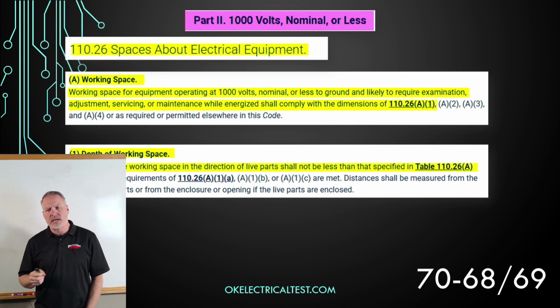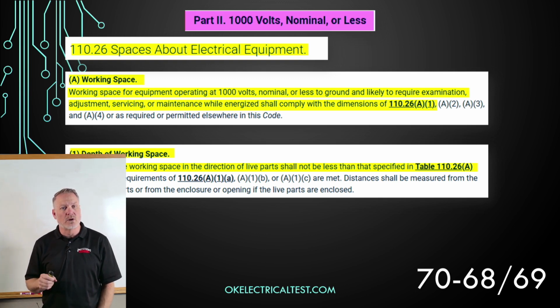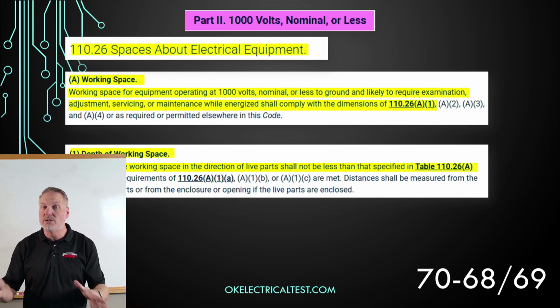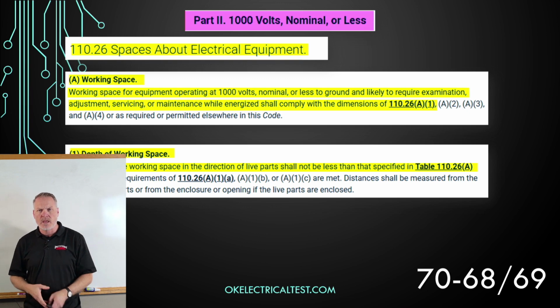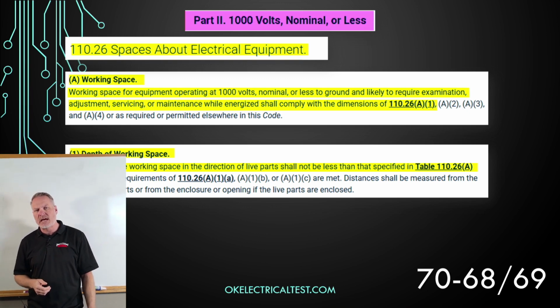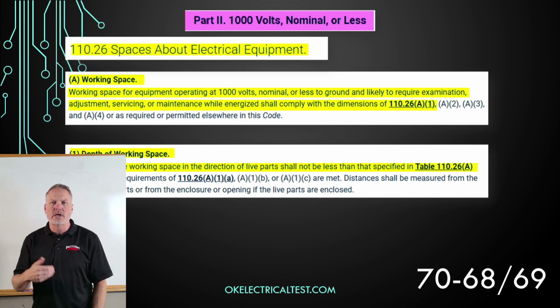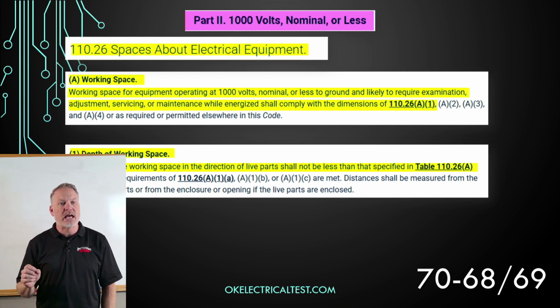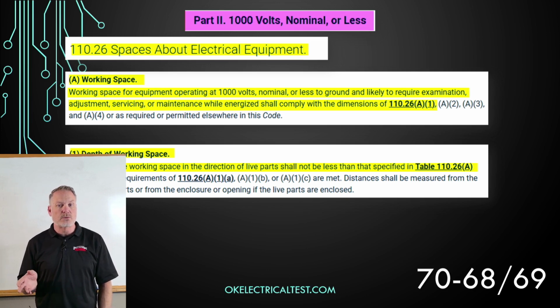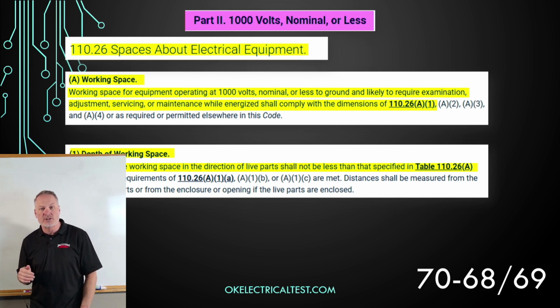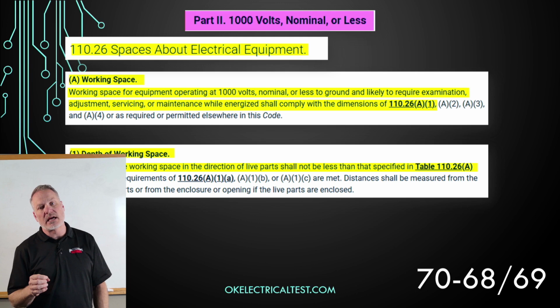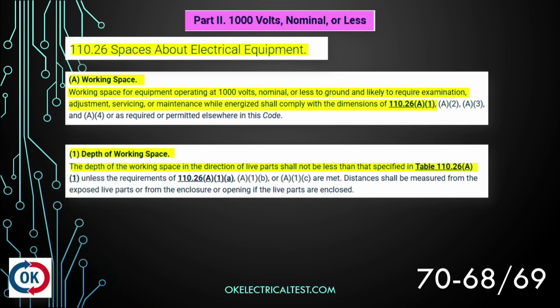Let's go down to part 2. So page 68, spilling on to 69. Part 2 is dealing with only installations that are 1,000 volts nominal or less. So remember, part 1 was general regulations. Now we're getting more specific. Hey, by the way, these regulations are only for 1,000 volts and under. And so we're going to take a look at 110.26, spaces about electrical equipment. And we're going to go to letter A, working space. Down below there, we're going to highlight working space for equipment operating at 1,000 volts nominal or less to ground and likely to require examination, adjustment, servicing, or maintenance while energized shall comply with the dimensions of 110.26(A)(1), (A)(2), (A)(3), and (A)(4), or as otherwise required or permitted in this code.